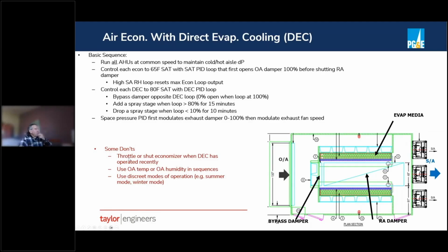Some important things not to do with air economizing and direct evap: you don't want to shut or throttle the economizer when the direct evap has operated recently, at least when you're operating it for cooling. If you're operating it for humidification, that's a little different. But what can happen if you're trying to do cooling is that if you overshoot and start to shut your economizer, there's still moisture in that media, and you can build up the humidity level in the space. So whenever you're on direct evap for cooling, you want it to be a once-through system. You want to be on 100% outside air.